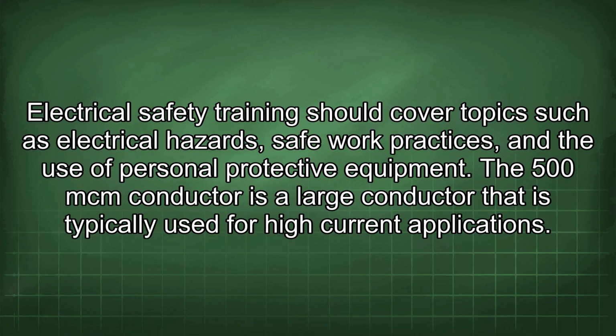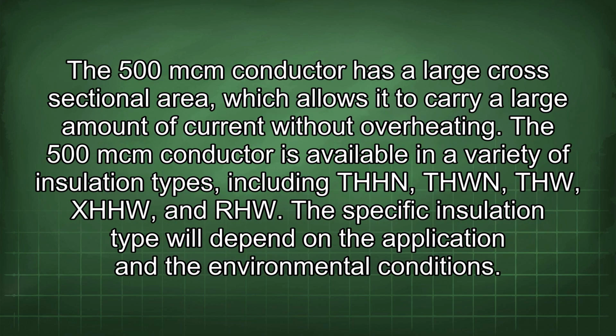The 500 mcm conductor is a large conductor that is typically used for high current applications. The 500 mcm conductor has a large cross-sectional area, which allows it to carry a large amount of current without overheating. The 500 mcm conductor is available in a variety of insulation types, including THHN, THWN, THW, XHHW, and RHW. The specific insulation type will depend on the application and the environmental conditions.